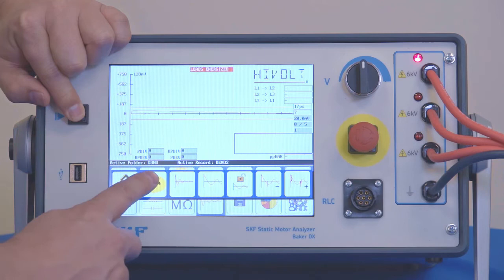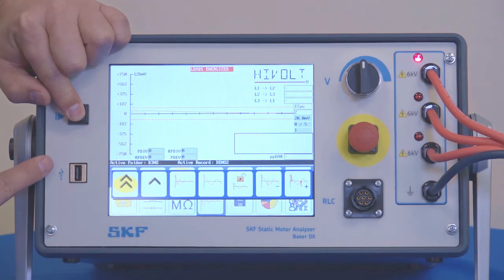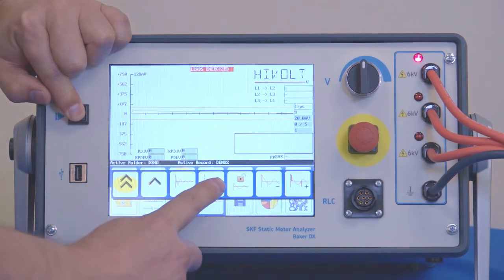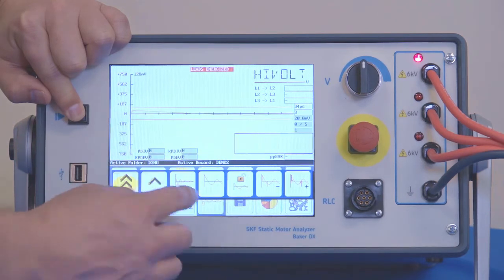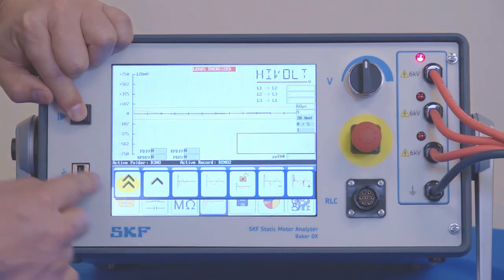You have your slow ramp and fast ramp. I'm going to select the fast ramp. Then you have these range scale settings similar to the normal surge test and get those so that your waveform takes up the screen.